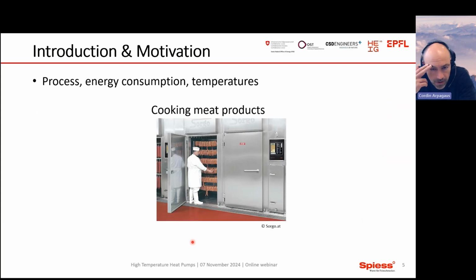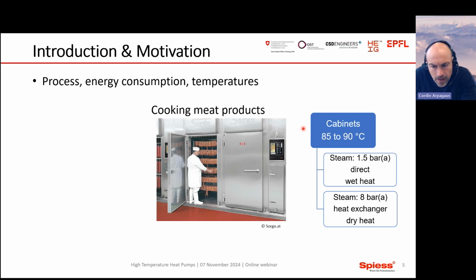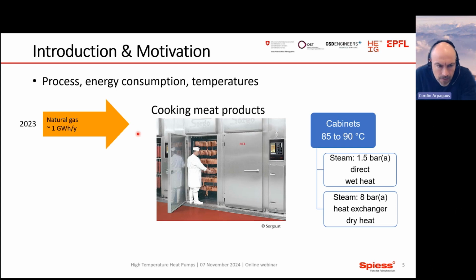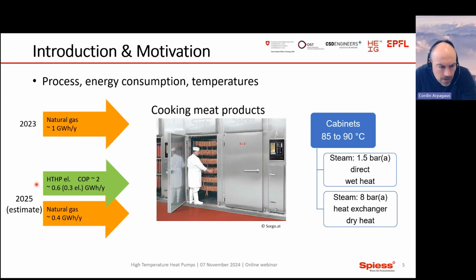So the temperatures and consumption and process: they have this cooking meat process. They have such cabinets where they cook the meats, the sausages at 85 to 90 degrees, and they use low pressure steam for direct heating of the meat. And they also have a second network with 8 bar for the heat exchangers to produce dry heat. Today they have a gas boiler, roughly 1 gigawatt hours per year energy demand, and in the future they could consider an electrically driven heat pump covering a share of this heat demand. That was an estimate at the early beginning.